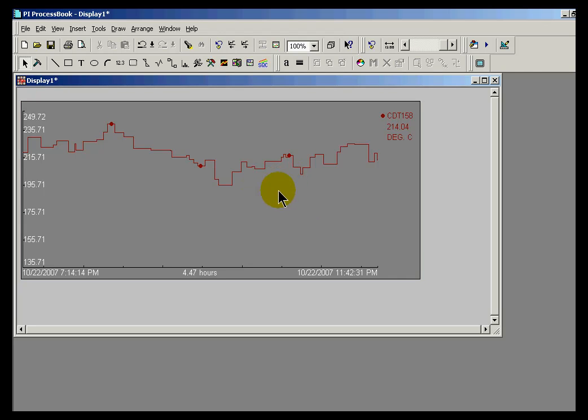Now this does have implications when it comes to how data compression is done. As we go through the class, you'll notice that we don't store every single value — we're storing values only when they reach peaks and valleys. Not only does this affect how it's displayed, but there are some subtle changes to the data compression algorithm. When a tag has Step turned on, the compression test is done more like a straight boxcar test, where we're not checking for slope anymore, just checking for going beyond the dead band.